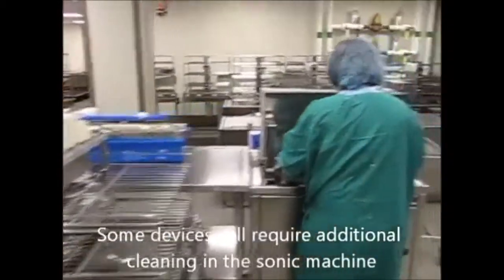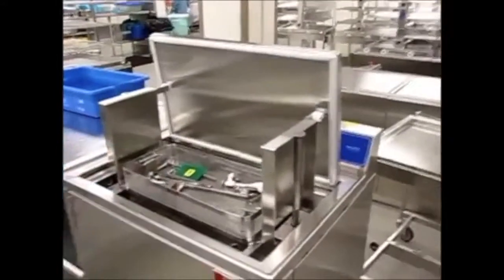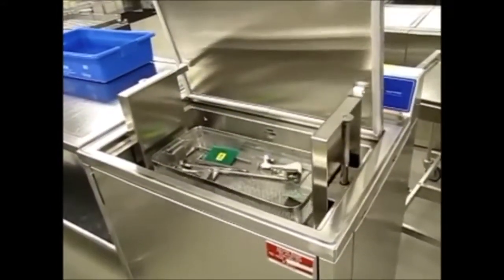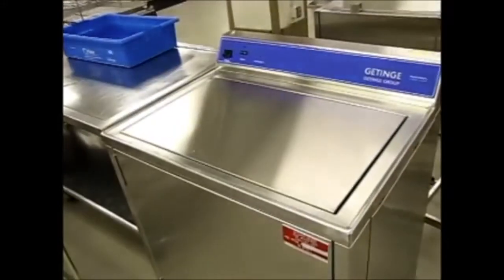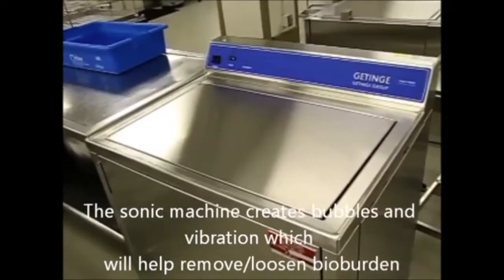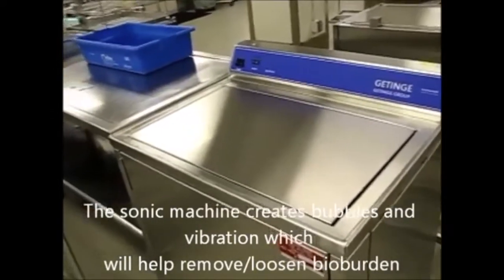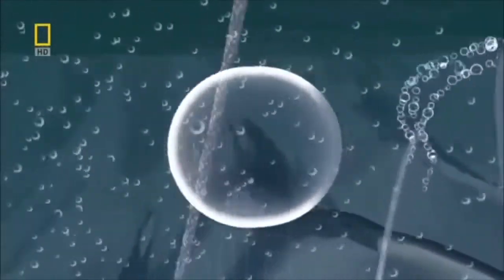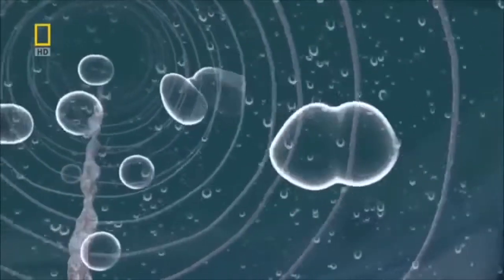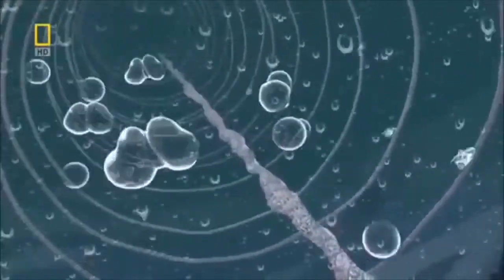As the ultrasonic waves spread through the detergent solution, they produce alternating tensile and compressive forces that oscillate at the same frequency as the transducers that produce them. These oscillating forces cause millions of microscopically sized cavities to form. Once the critical threshold is reached, these cavities violently implode, causing submicroscopic voids to form by a process known as cavitation. These powerful suction effects are due to high-energy hydraulic shock waves. These shock waves can reach temperatures as high as 10,000 Fahrenheit and hydrostatic pressures as high as 10,000 pounds per square inch.